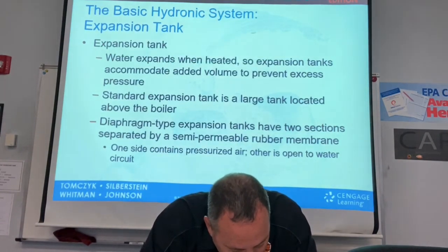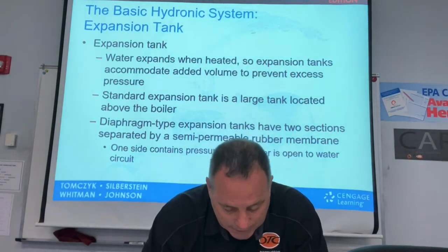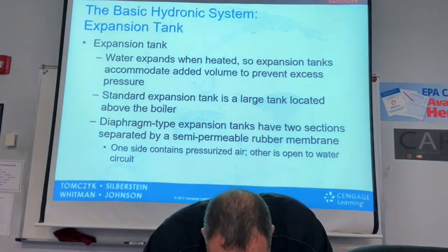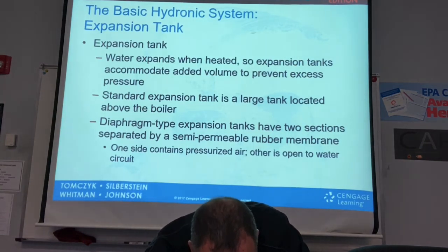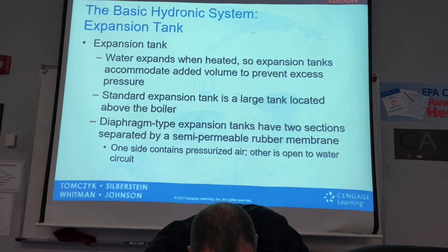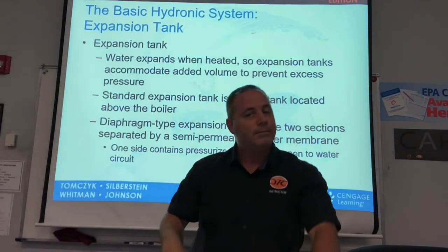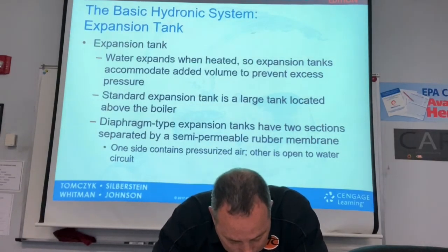There are two types of expansion tanks that accommodate the overload of heated water pressure. The first is called a compression tank — simply a steel tank filled with atmospheric air. As the water pressure increases from heating, the air creates a cushion of space.